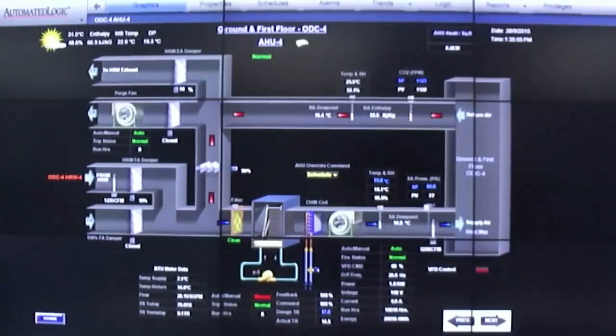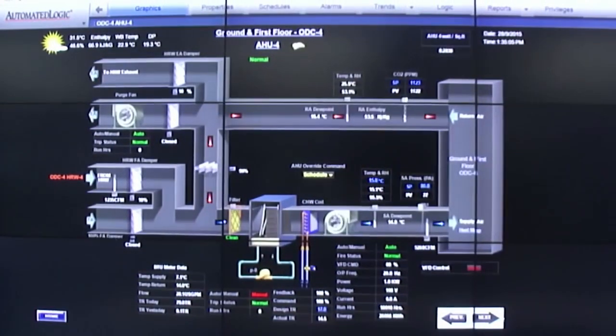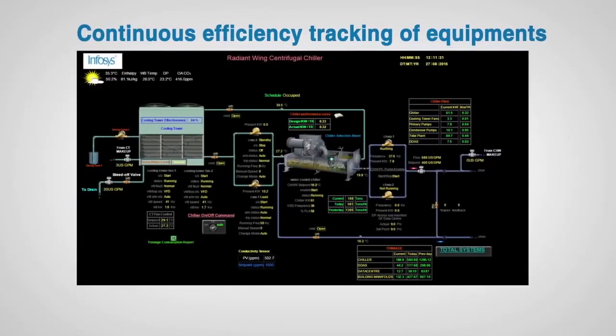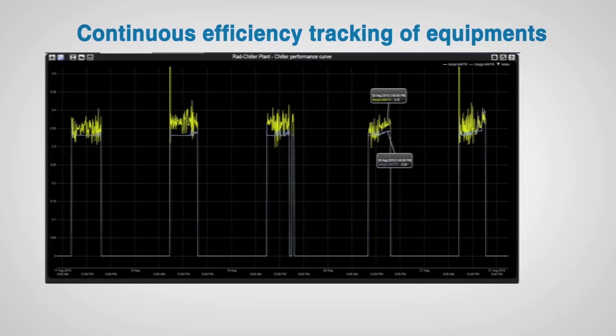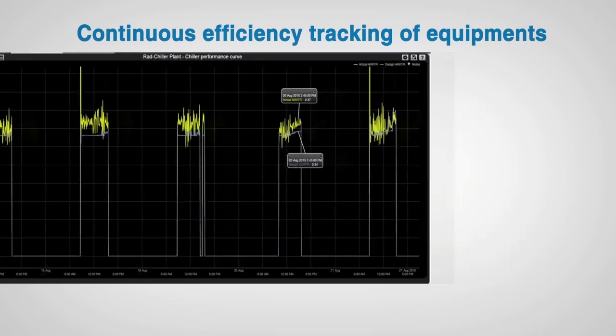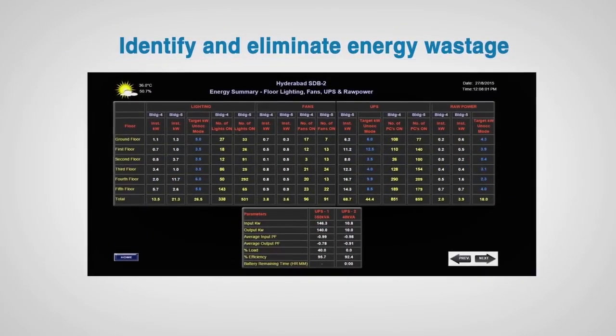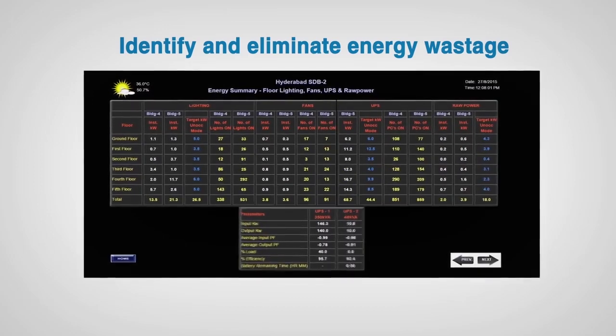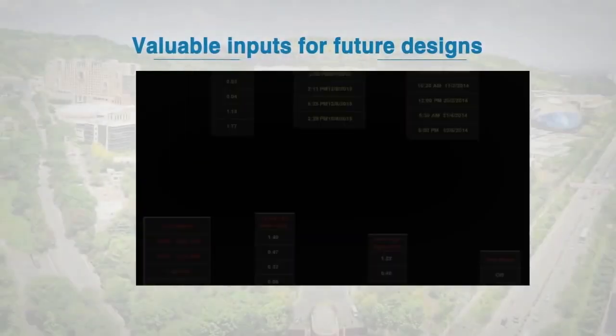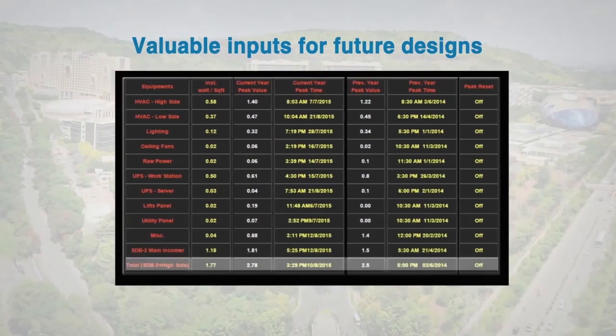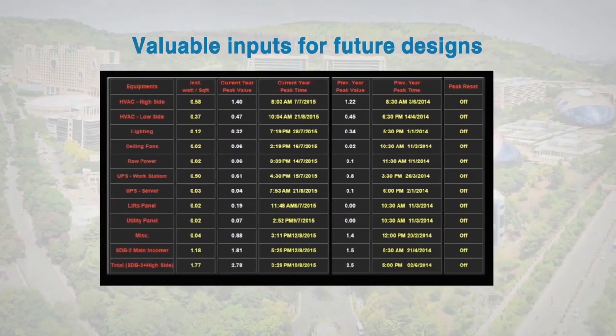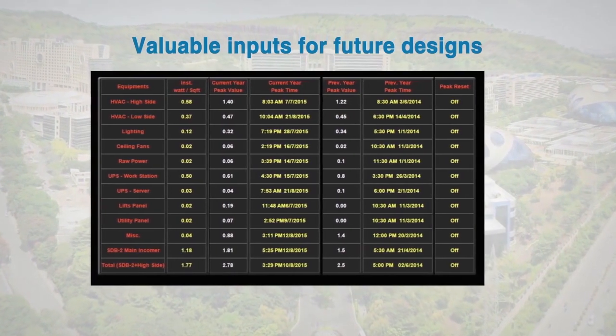Flow meters, energy meters, and temperature sensors track the real-time efficiency of major equipment like chillers, comparing continuously against design values. Floor level sensors and metering ensure energy wastage is eliminated. Measured data from our buildings is validated against design values and provides valuable input for future designs.